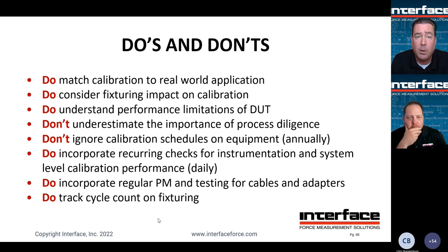Do incorporate recurring checks for instrumentation and system level calibration performance. This means checking electronics, checking rig performance to make sure that there's nothing out of the ordinary, and checking instrumentation to make sure it's reading its input correctly and is not identifying errors. The last thing you want to do is get through a day of calibration only to discover that there's an issue with the acquisition board and it's been reading off by 5% all day long. Or worse yet, you've already shipped load cells and said board was off.